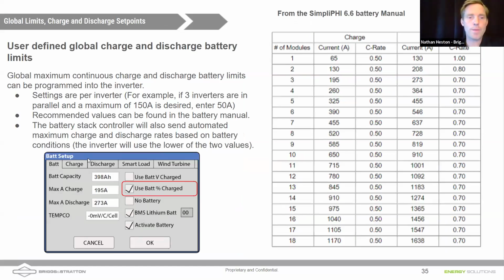So it should automatically communicate that there's a certain number of amp hours inside the battery. For a single stack, you'll see that appear as 398. The maximum charge rate is a global maximum charge rate under that first battery charge. What do I mean by global, Daniel? That means it can come from any source. Yeah, from all the sources combined, we will not exceed this programmable value. Now, you can program that to whatever you like.